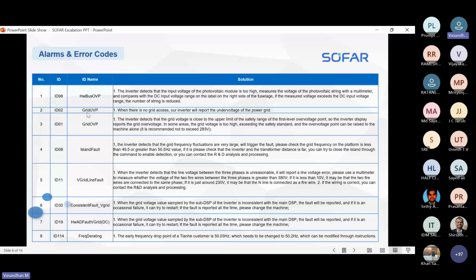And the next is grid UVP. Grid UVP is nothing but there is no grid; the alarm will show on the display as grid UVP. For example, grid OVP means over voltage protection. Whenever you install the inverter and get grid OVP or UVP, we need to set the parameters online or offline, based on the capacity. And island fault: island is nothing but frequency fluctuations. Then we can check the frequency range. The minimum to maximum we can set in the inverter is 46.5 to 52.5. So next one is ID11, grid line fault. This is also one of the grid issues. That means we need to adjust the value on the grid side.